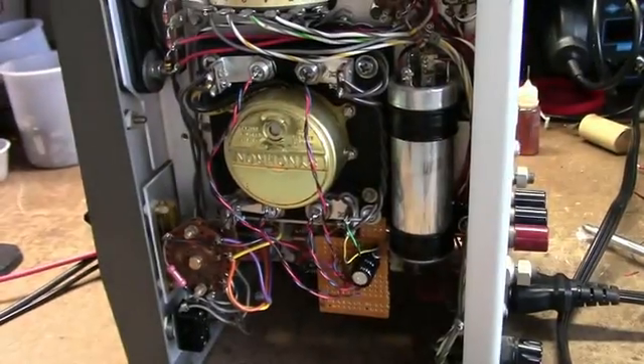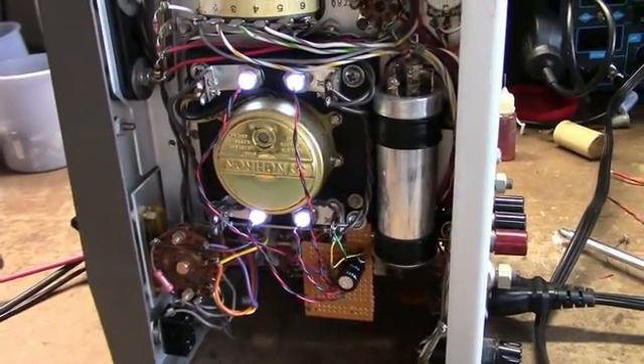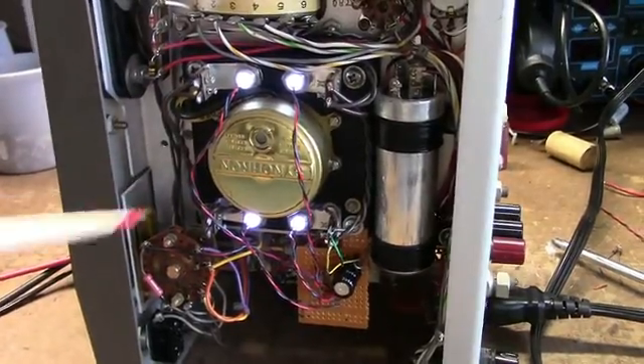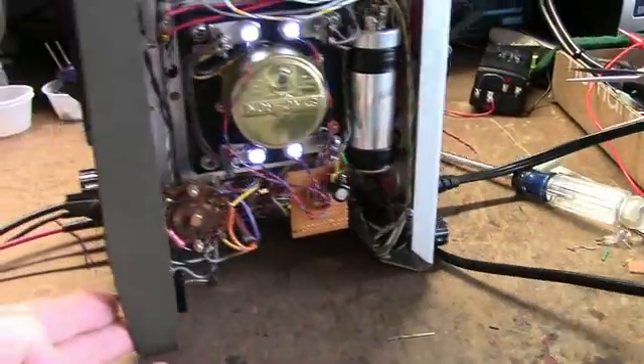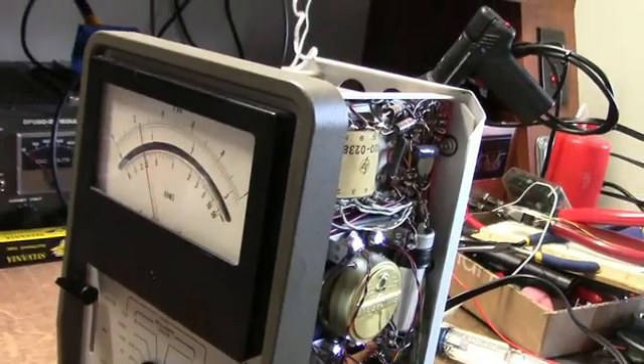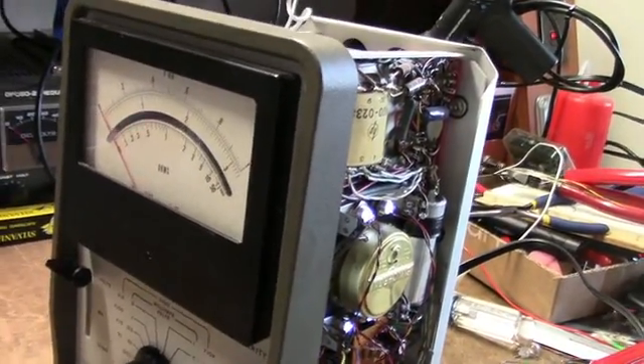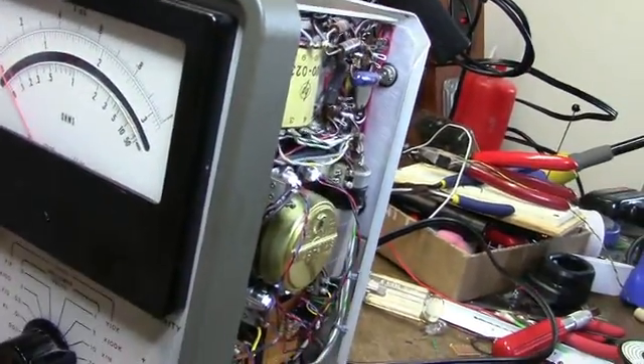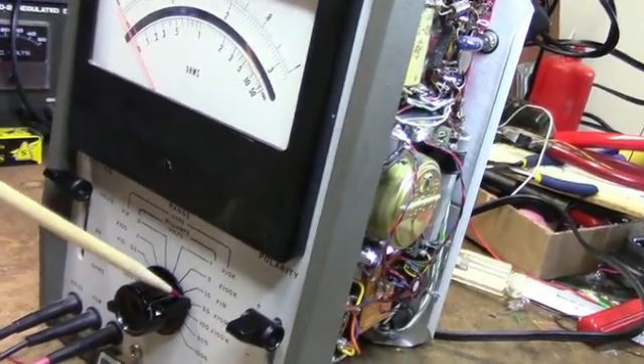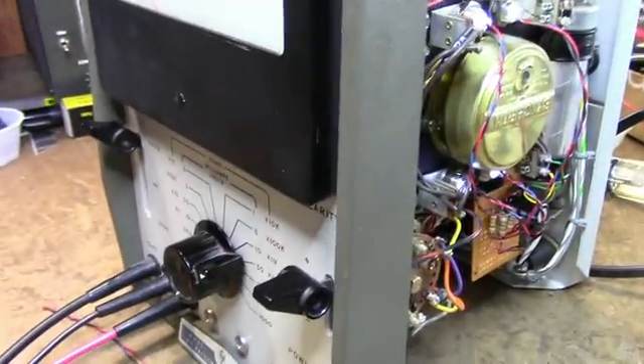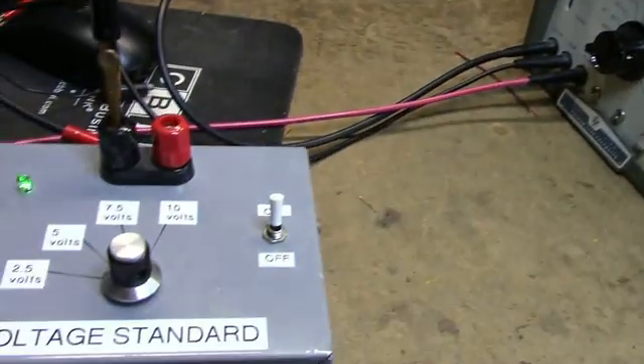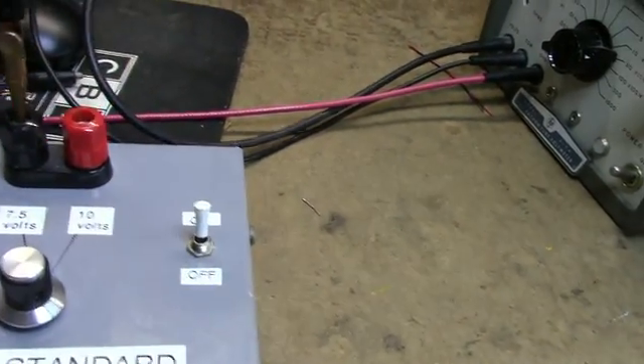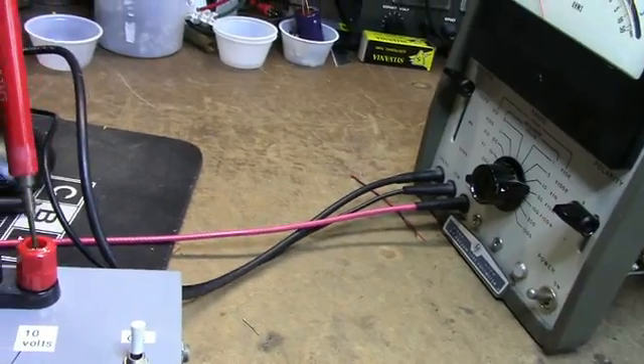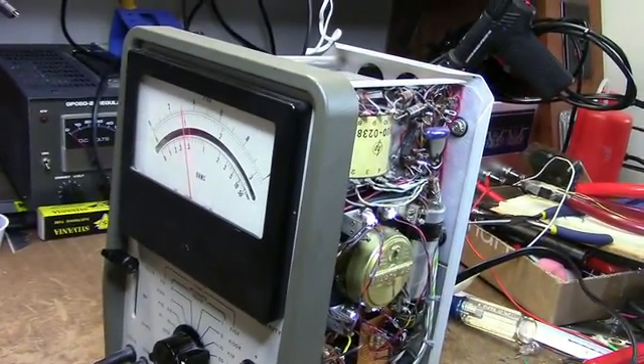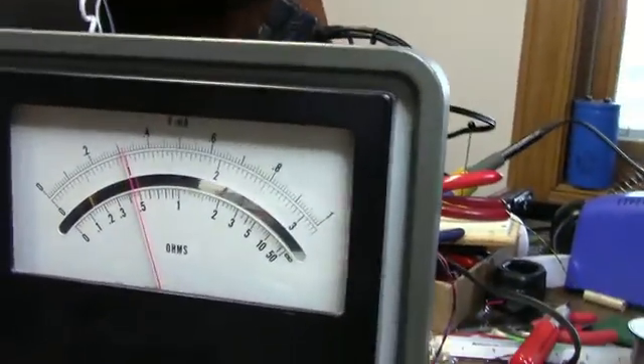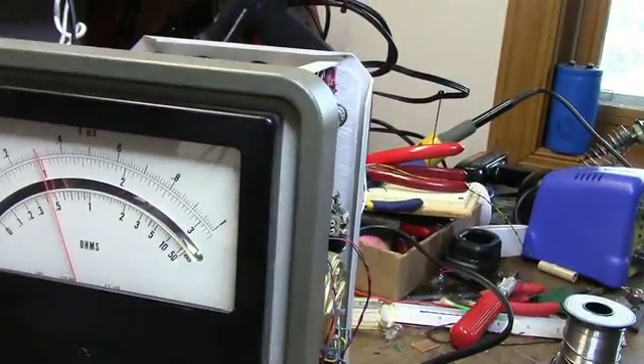So I'm going to turn it on now, and you can see the four LEDs lit. And the meter went through its normal, went to the right, and then it settled back down. I've got it on the 30 volt range, and I've set my voltage standard on the 10 volt range. And now I'm going to apply 10 volts. That's pretty close to 10 volts.